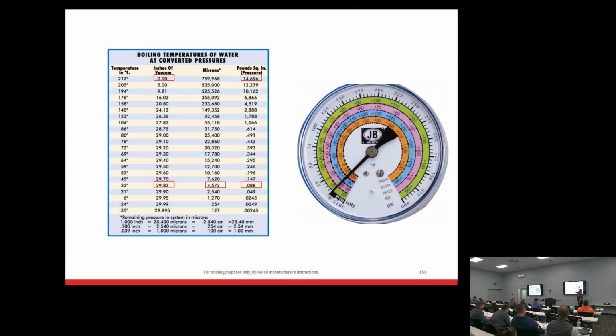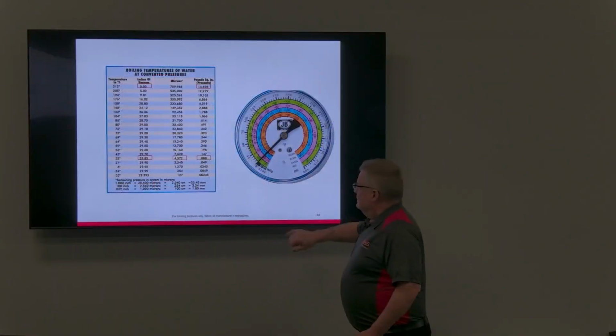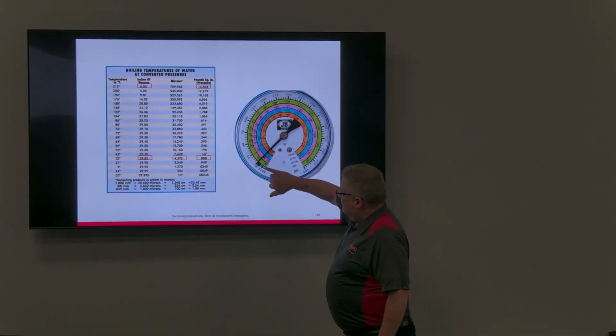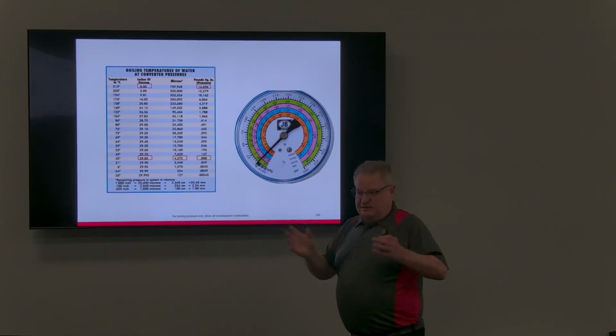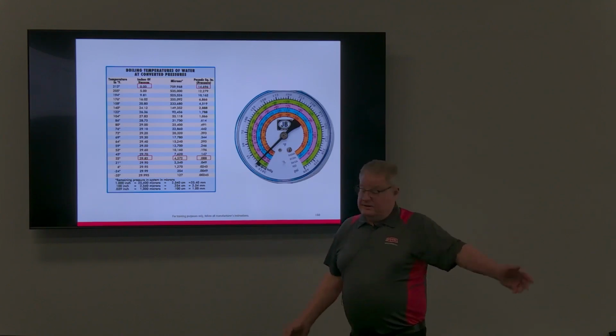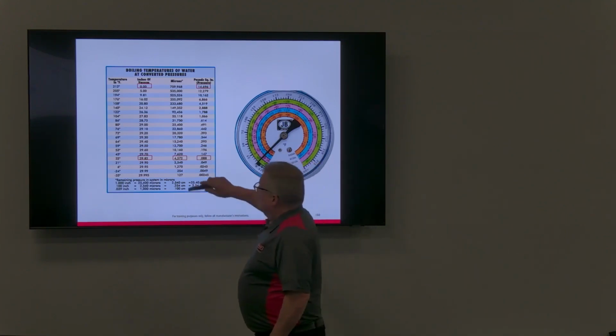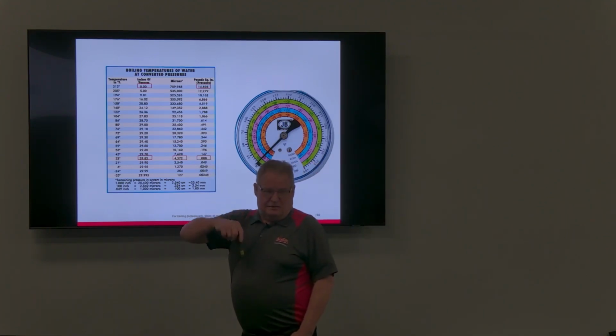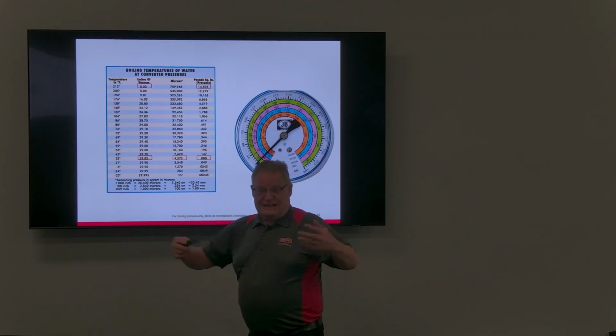Now, I always said if I started a business, I'd make all my new techs use analog gauges for the first 2 years, and the PT chart, because then they understand what they're doing. The one thing I wouldn't do is this, because this gauge here is absolutely worthless for vacuum. So 30 inches, between 29 and 30 is that last line there. And I like to show this just because sometimes the boss tells us to do it. Why do we do it? Well, because this is why we do it. So we need to get water to boil in this room right now, right? If we have moisture in the system, we need to get it to boil to suck it out.